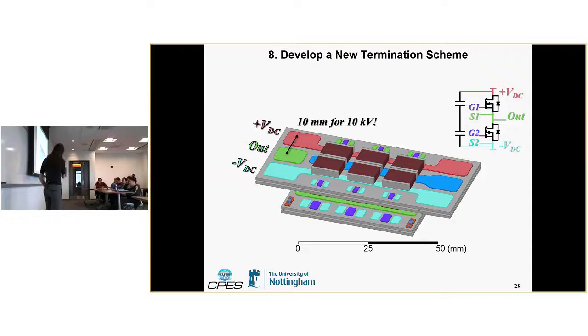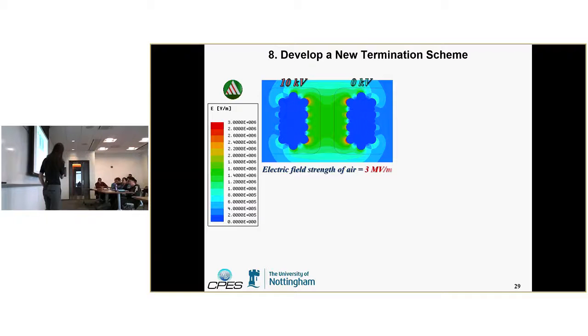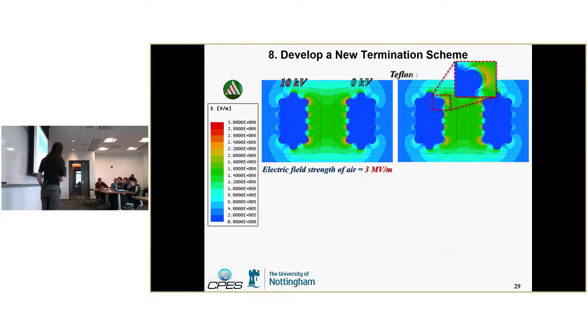Here's a top side view of two patterns, showing an electric field simulation with about 10 kV across them, spaced roughly 10 millimeters apart. This is a look at springs - we looked at bus bars, but because of their sharp edges they're not ideal for high voltage, so we considered more rounded geometries like springs or pins. The electric field strength of air is 3 megavolts per meter, and in these areas we're actually exceeding that, meaning you'd get partial discharge in the air - visible sparks and cracking. So we looked at a few different approaches.